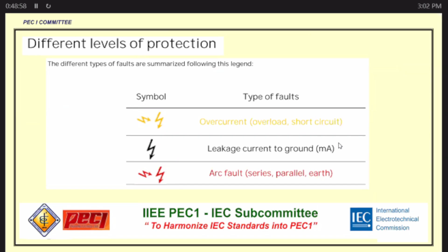Looking at the miniature circuit breaker, what can it actually protect against? The miniature circuit breaker could only provide overcurrent protection. But that depends on what we mean by overcurrent. If you look at the time current curve or TCC curve — who here is familiar with that? If you already have 200% overcurrent, how many seconds will that take to trip? How many minutes will that take to trip? As electrical engineers we should be aware of that, because you might think that once you overload by 10%, it automatically trips. It's not like that yet — there's what we call the time current curve, it might take 2 hours. So sometimes you're already burned by then. How about 200%? At 200% overload, will it trip immediately?